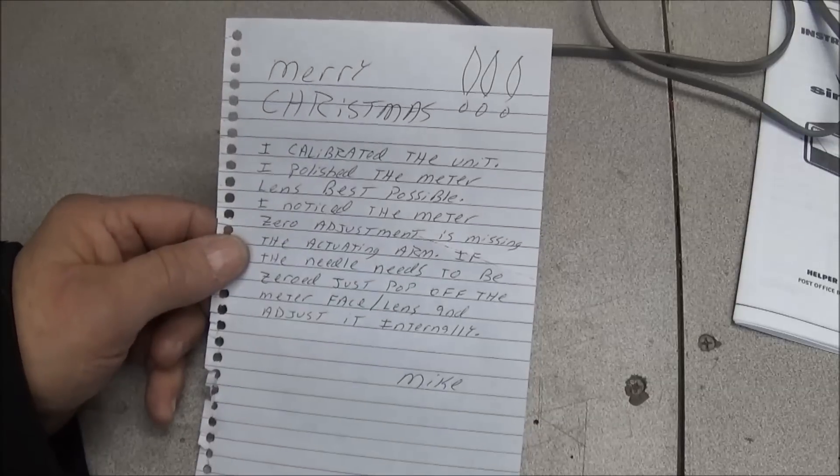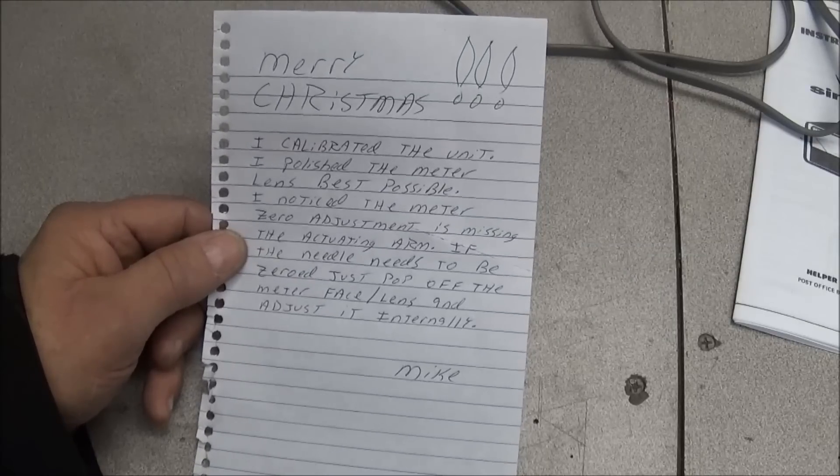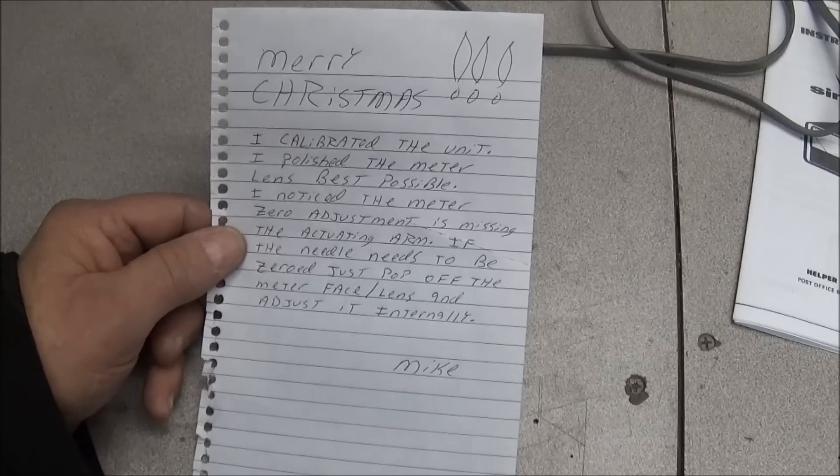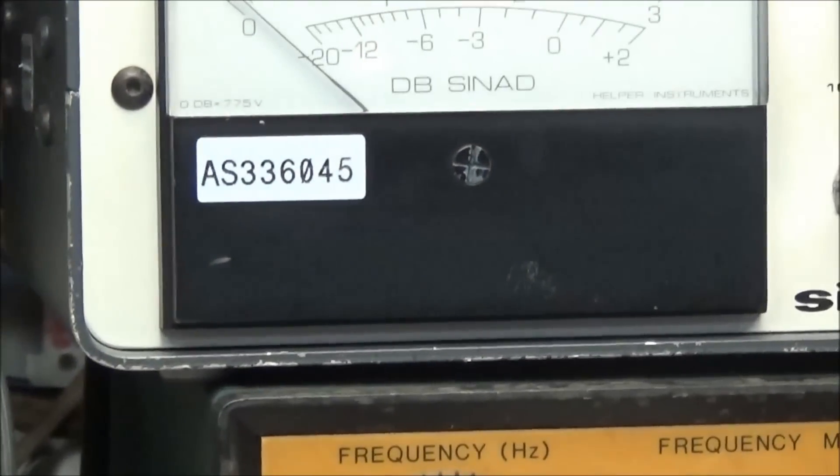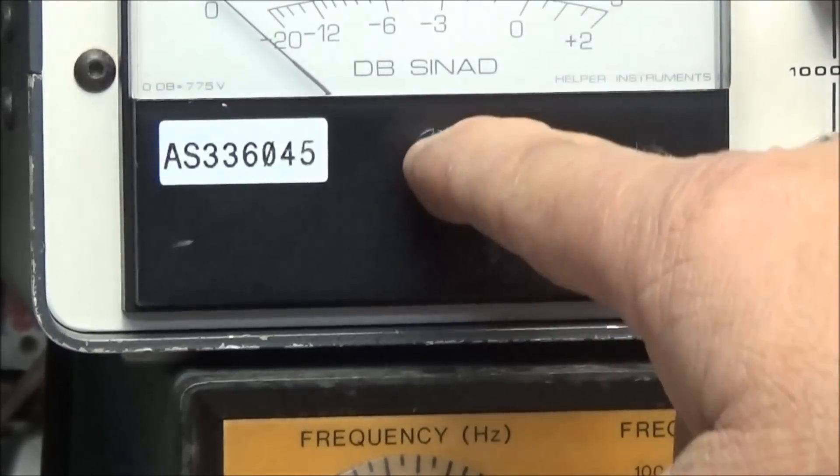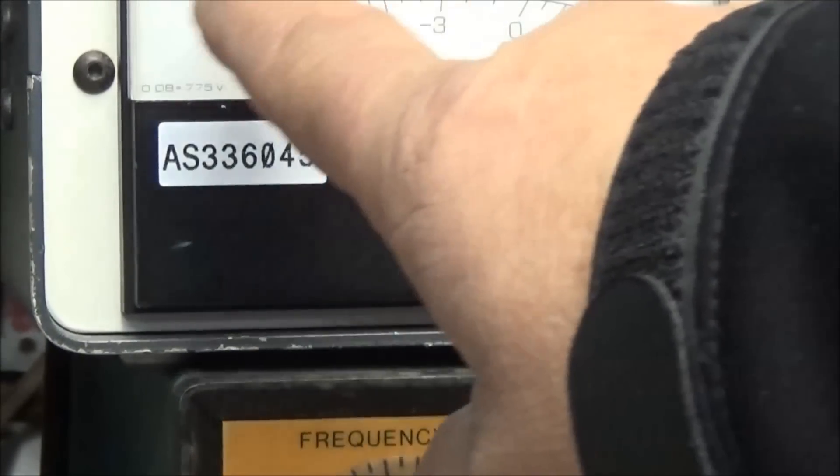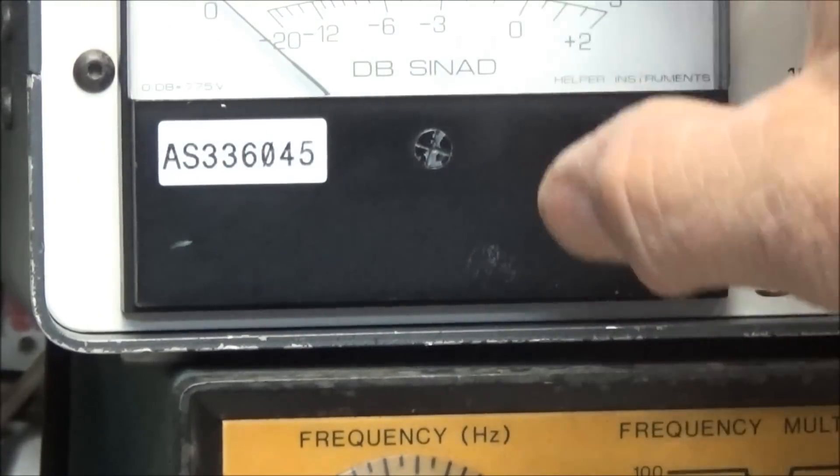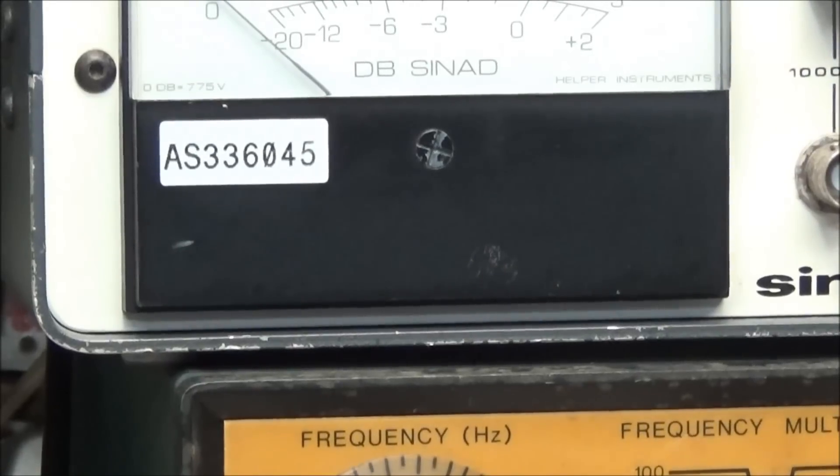This old note says Merry Christmas. I calibrated the unit, I polished the meter lens the best possible. I noticed that the meter zero adjustment is missing or the activating arm. If the needle needs to be zeroed, just pop off the meter face lens and adjust it internally. And what it is, on the back, you see I've already got me a home for it right there. On the meter is a little screw that you can turn, and on the back of that screw is a little arm that sticks off to one side, so there's a little fork on the meter calibration. By turning this, it just moves it back slightly to zero the meter. So since that one's broken, you can turn it and it won't do anything. So all you have to do is just pop the lens off and move the little fork back and forth manually. No big problem, be very easy to do.